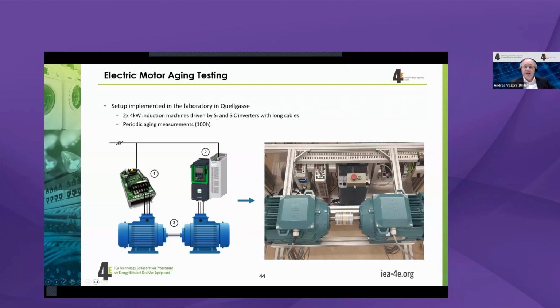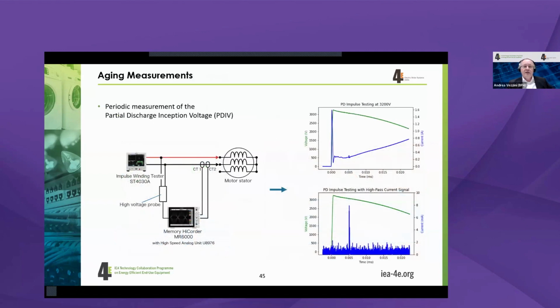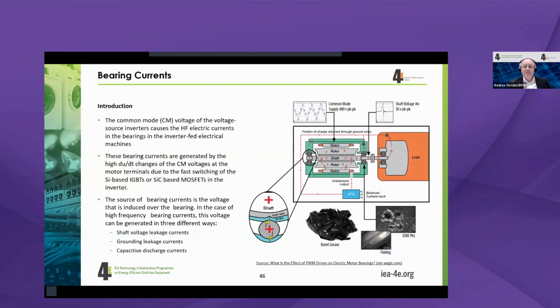We have a silicon carbide inverter and we have a silicon inverter. The silicon inverter drives the motor and the silicon carbide then drives the brake, and you have a circle here, and we do periodic aging measurement using partial discharge inception measurement, where we try to find out if with more and more aging of the insulation, we have more partial discharge. Partial discharge, you can see here, is this small current here. And we are using a high-pass filter to detect this. This is an ongoing test in our lab.